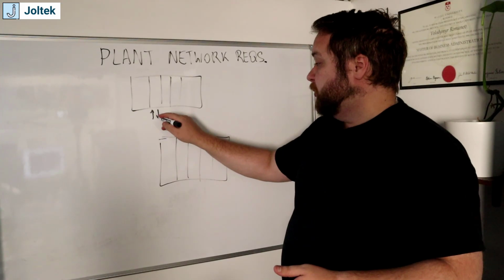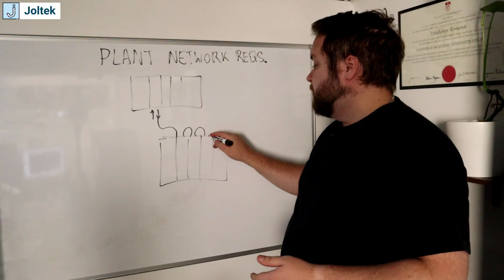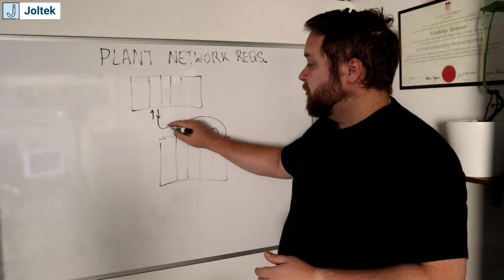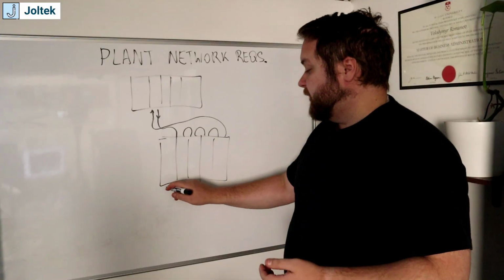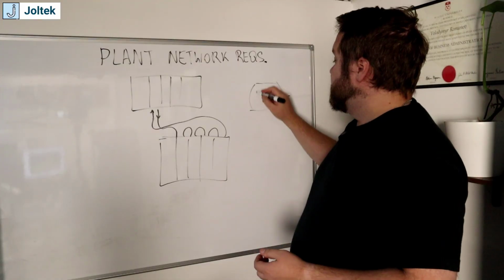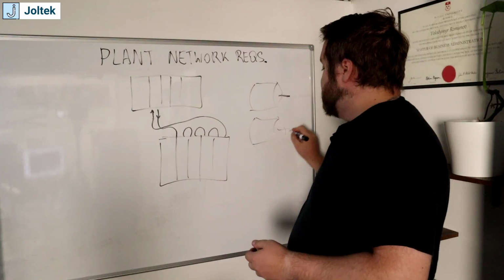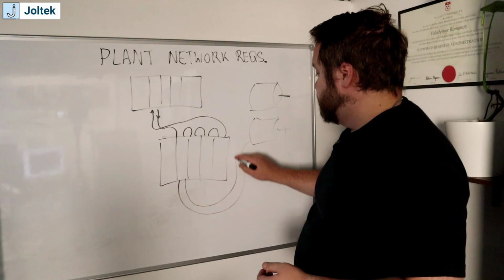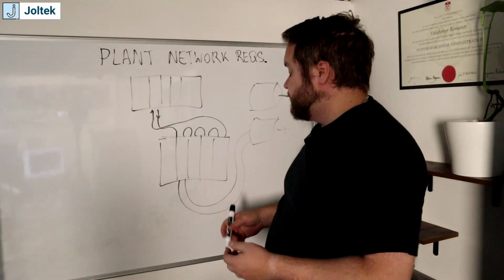And so the output of this card is going to go into module 1, then it's daisy chained to 2, 3, obviously hitting as many cards as it needs, skipping the blanks, and then this would return back to the input of your SERCOS module. And so this way you would have basically servo drives on the other side. And again, I'm just making a very basic drawing of a couple of motors that you would have in the field. Each one of these cards would then, in this specific case, the ones that I had worked with, have 2 different cables, one for power and one for auxiliary for all the signals that it's sending.